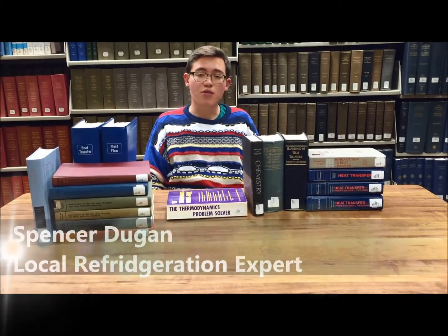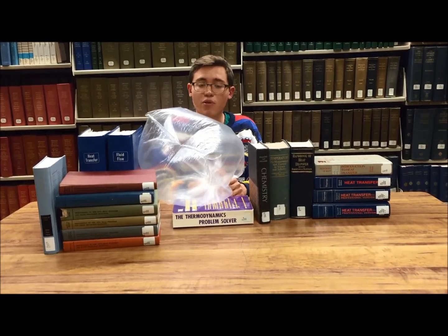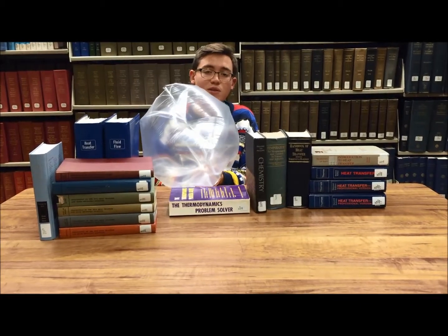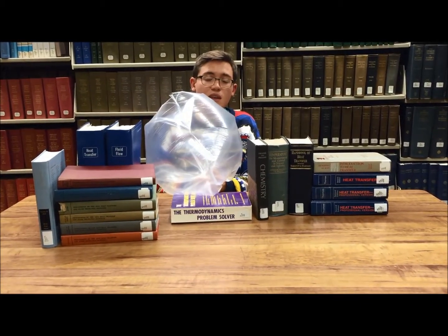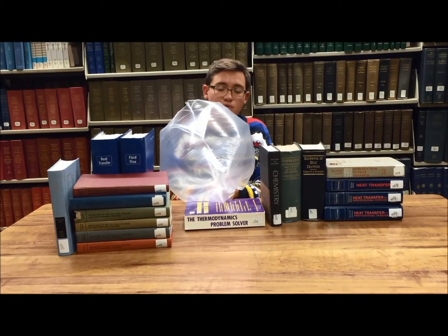While most systems use a thermostatic expansion valve, this valve is designed to ensure that a minimal amount of liquid enters into the compressor. So what this valve does is it functions similar to a balloon, and the temperature at the evaporator controls the temperature of a volatile liquid placed inside the valve. When a high temperature is sensed at the evaporator, the volatile liquid expands, causing the balloon to expand and exert a higher force upon the valve. This limits the gas produced by the valve, meaning that more liquid will come from the thermostatic expansion valve.